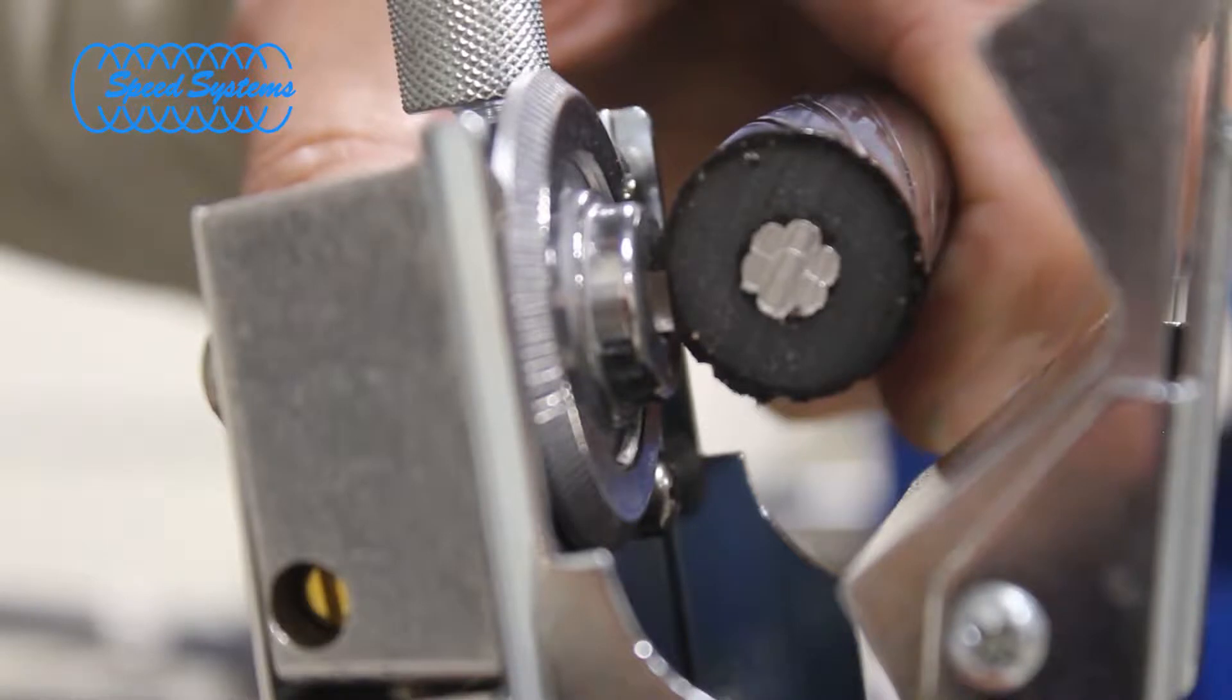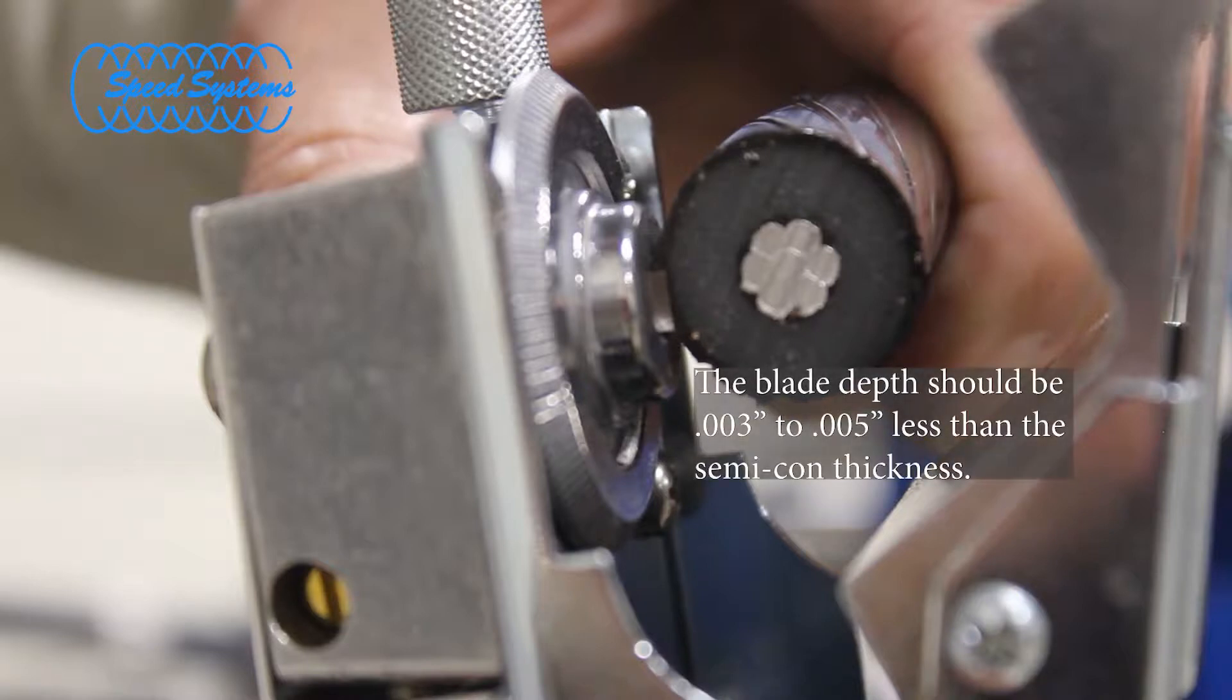Check the blade depth on a scrap piece of cable if one is available or by visually checking the blade at the end of the cable. The blade depth should be set to approximately 3 to 5 thousandths inch less than the SEMICON thickness.